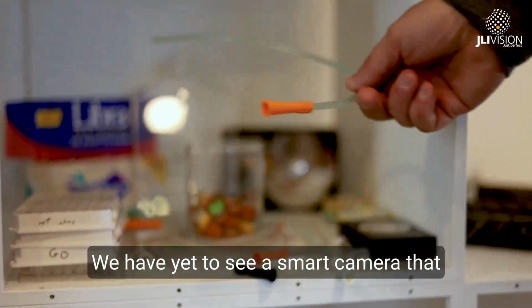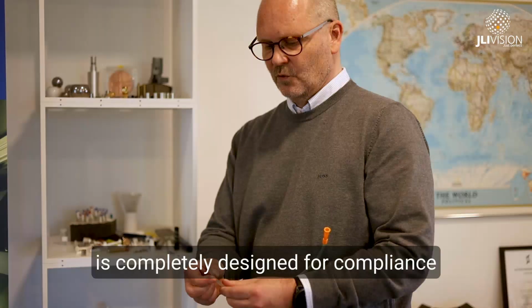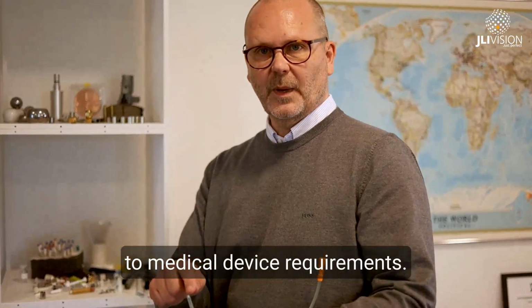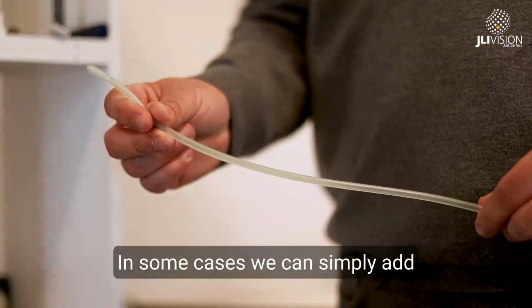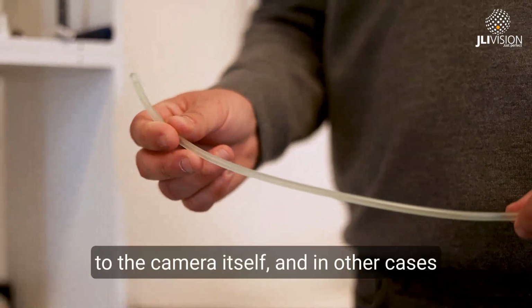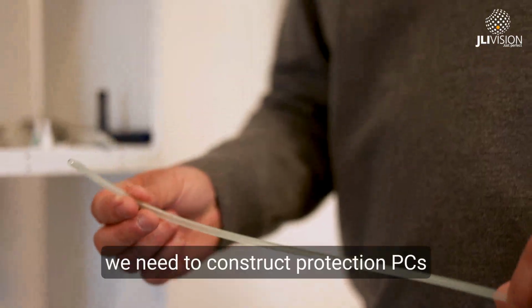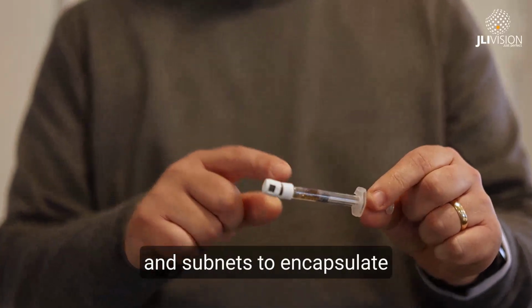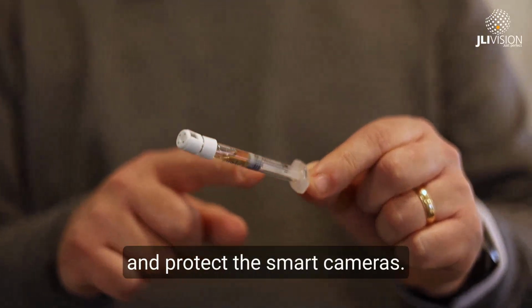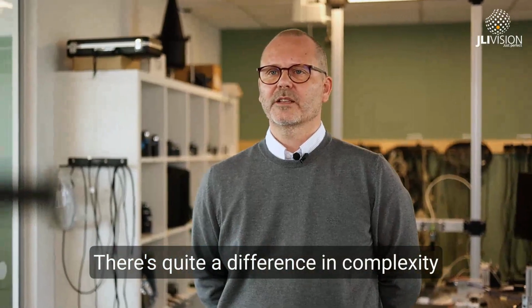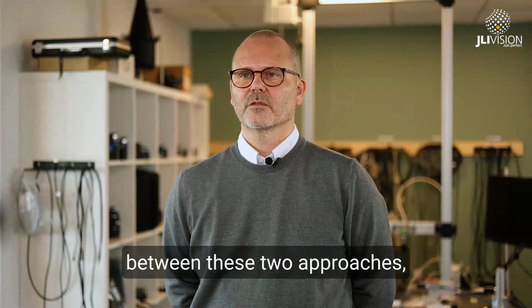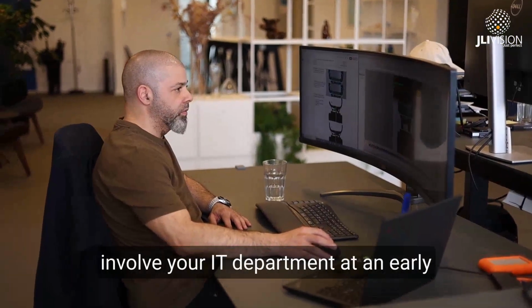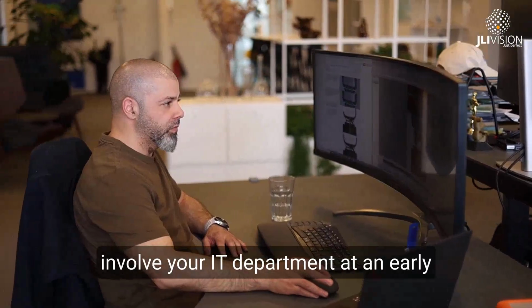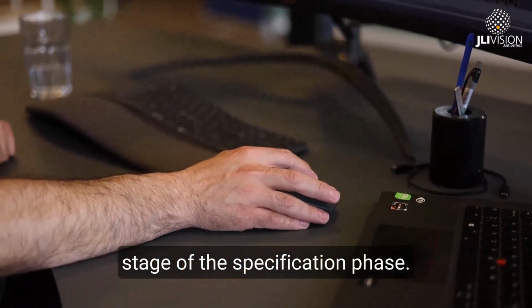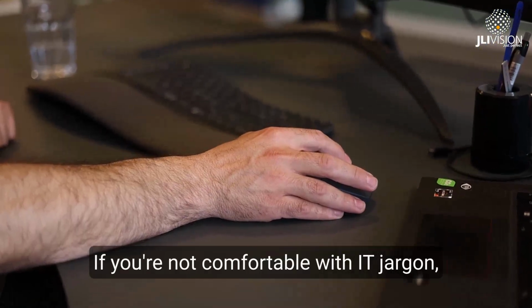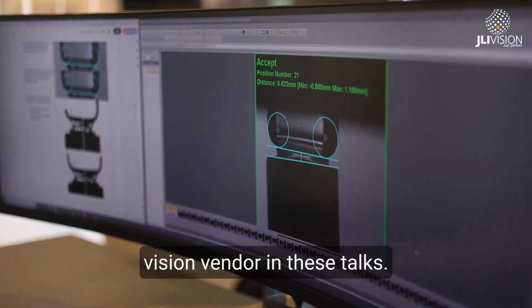We have yet to see a smart camera that is completely designed for compliance to medical device requirements. In some cases, we can simply add the missing functionality to the camera itself, and in other cases, we need to construct protection PCs and subnets to encapsulate and protect the smart cameras. There's quite a difference in complexity between these two approaches, and that is why you should always involve your IT department at an early stage of the specification phase. If you're not comfortable with IT jargon, you should involve your vision vendor in these talks.